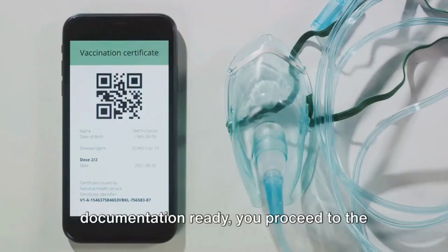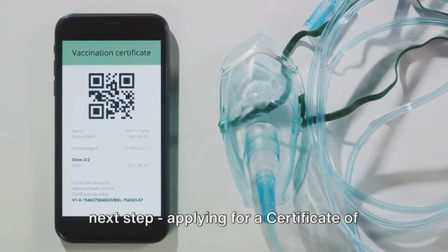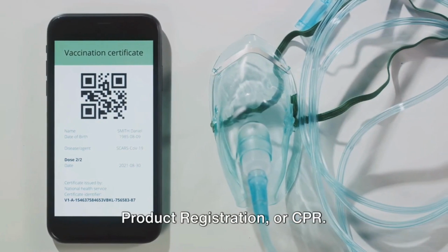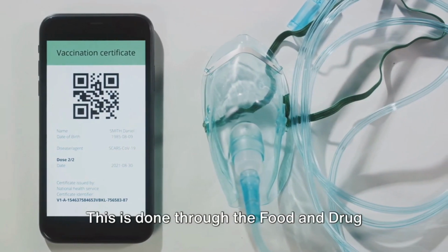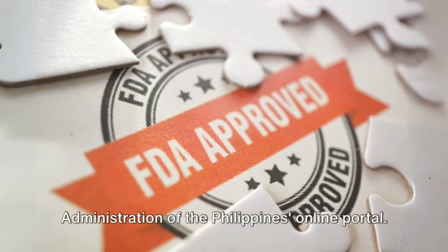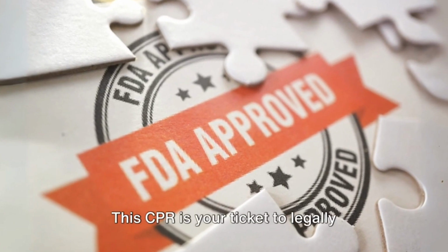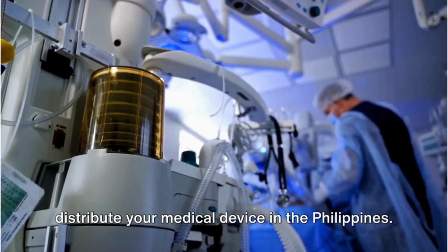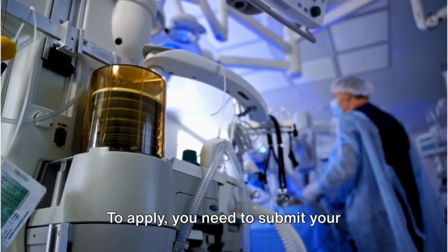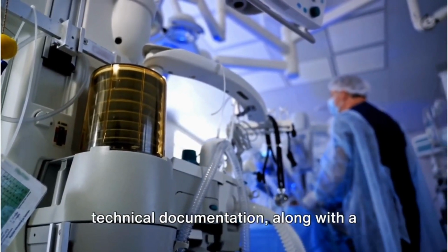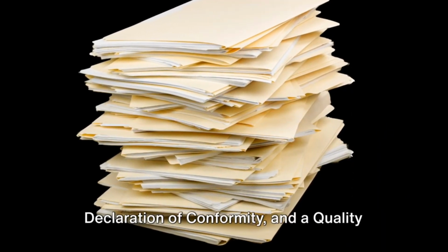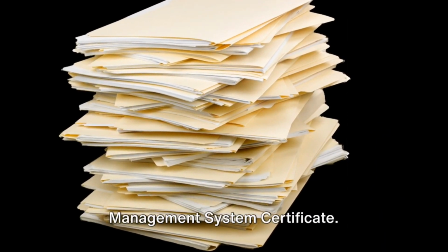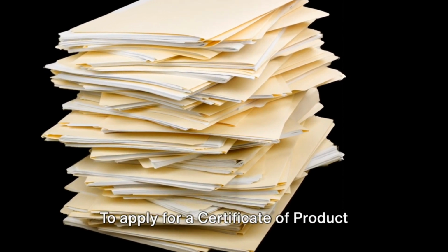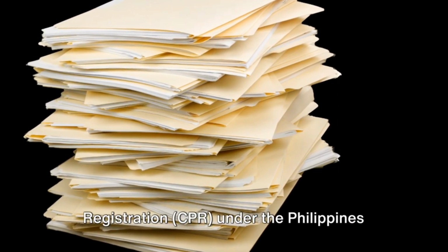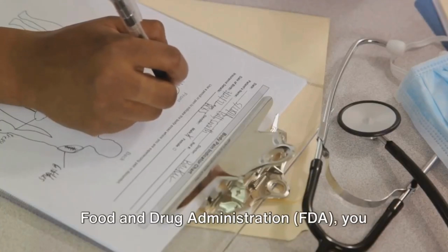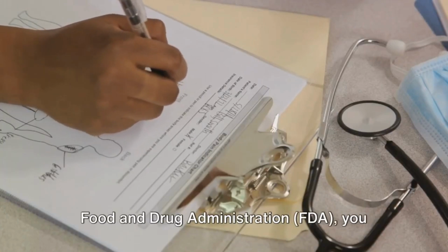Once you have your technical documentation ready, you proceed to the next step, applying for the Certificate of Product Registration, or CPR. This is done through the Food and Drug Administration of the Philippines online portal. This CPR is your ticket to legally distribute your medical device in the Philippines. To apply, you need to submit your technical documentation along with a declaration of conformity and a quality management system certificate.